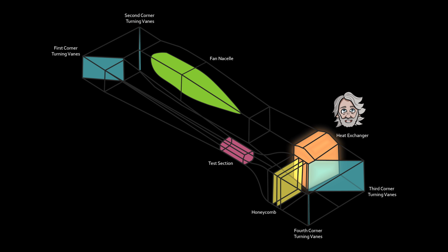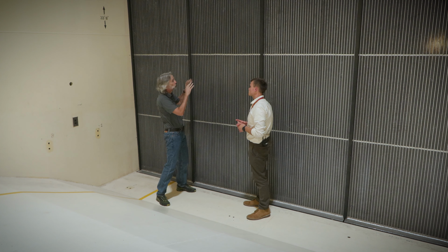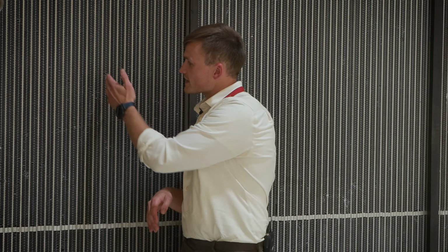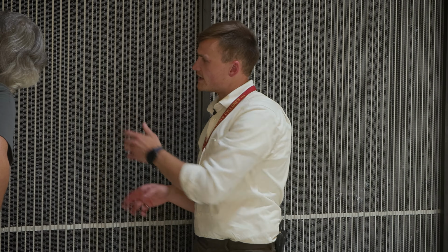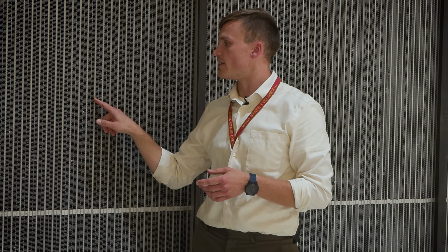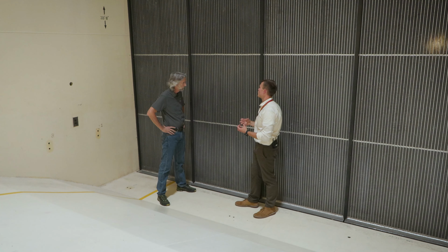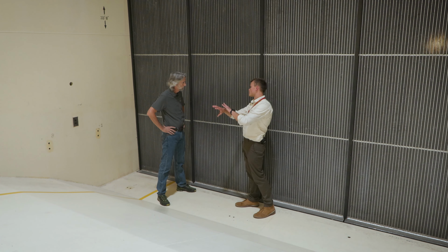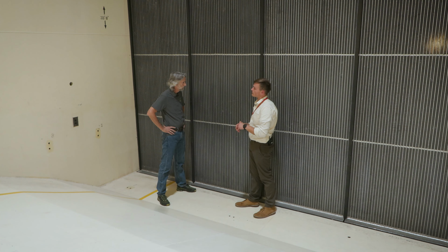All right, Eric, we were talking about it earlier, but this is actually that heat exchanger, and it looks like nothing more than a super giant radiator. That's right. So just like a standard radiator, there is some fluid, and it's pumping through these plates, and the fins that are attached to them are made out of aluminum, which has that really high heat transfer. And so it'll heat up this area here, and then we pump that water away from it, which is going to hold all of that heat energy, which then goes to our outdoor system. We actually have a water-to-water exchanger, which then we pump in an outdoor chamber. So we actually have a conversion, which is pretty neat and unexpected as compared to your filter at home.